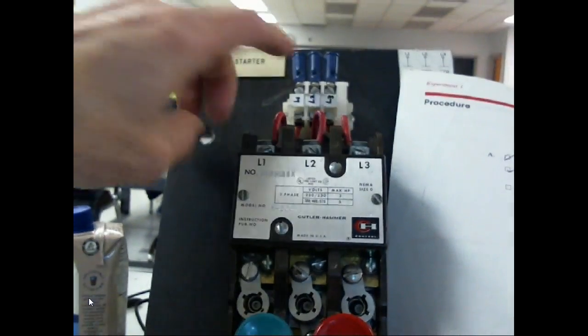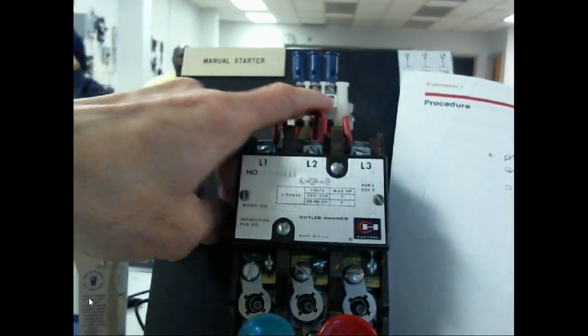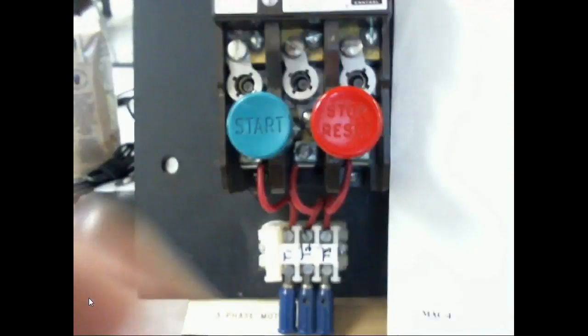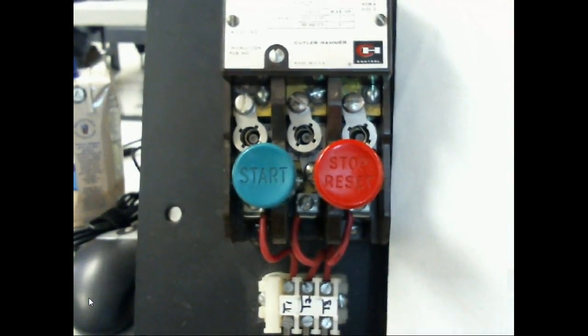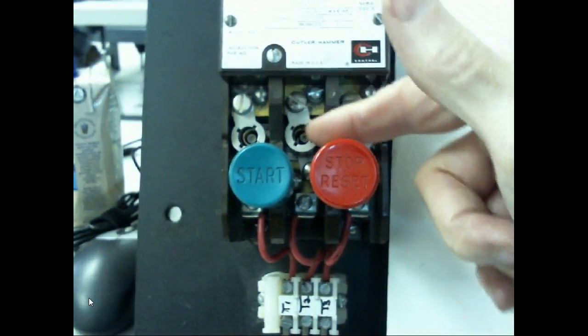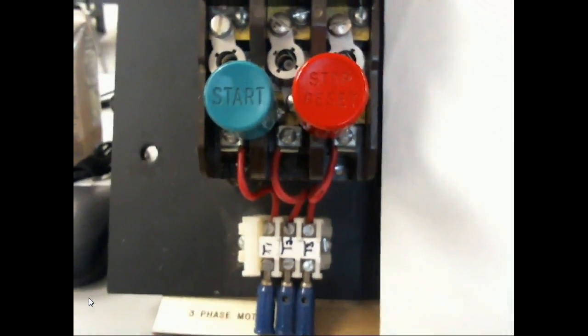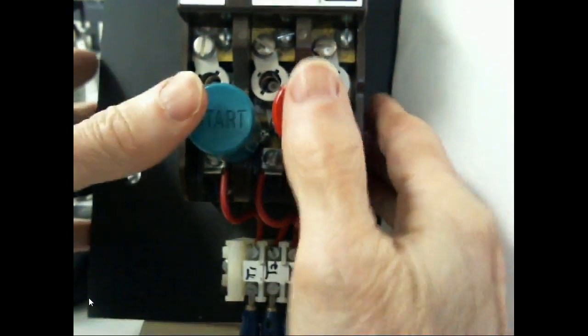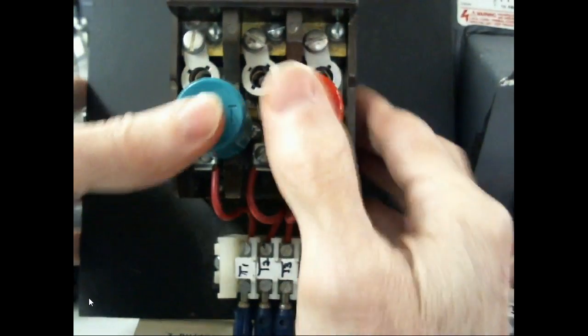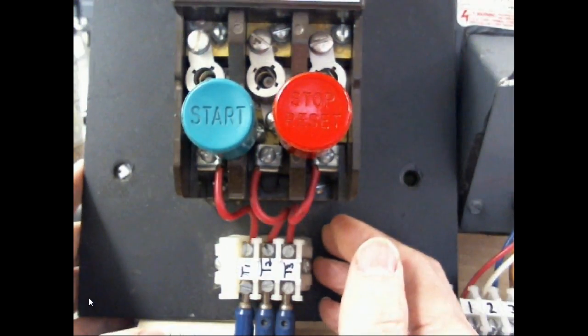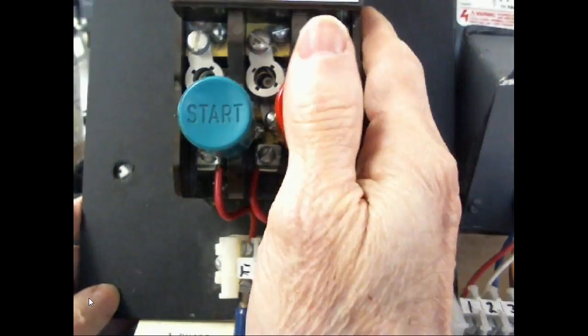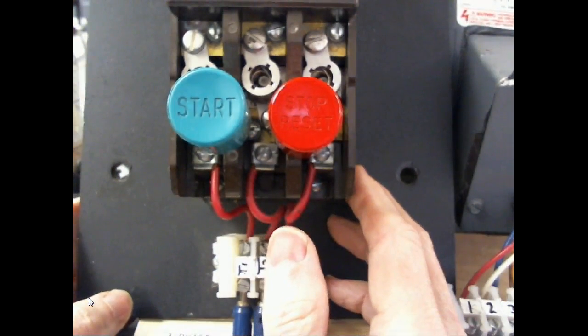Now here's the motor starter itself: L1, L2, L3 at the top, here's the overloads - everything is built inside, here are the heaters for the overload, and T1, T2, T3 on the bottom. This thing is spring loaded, so you can hear it snap. If you hit start and there's an overload, it'll automatically kick it out with this. Makes sense?